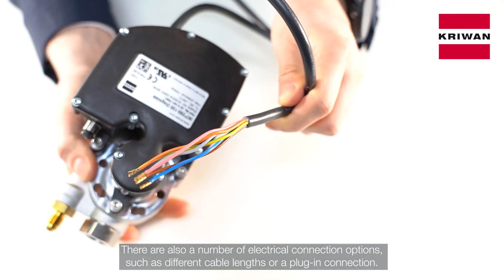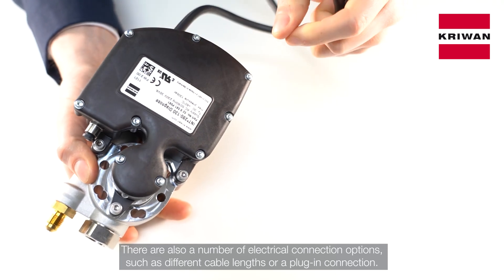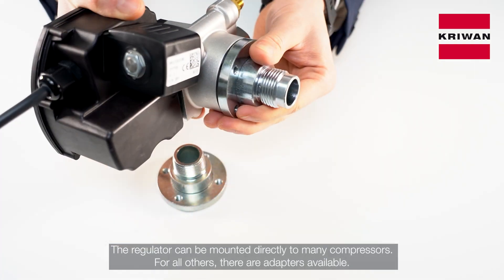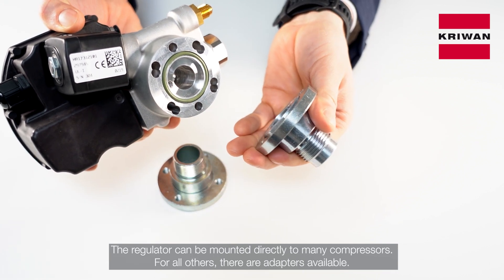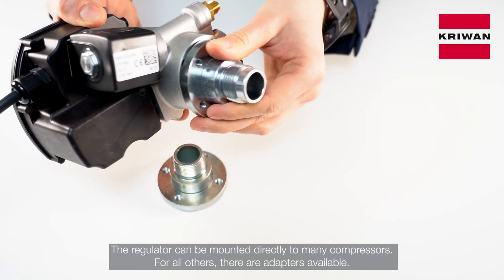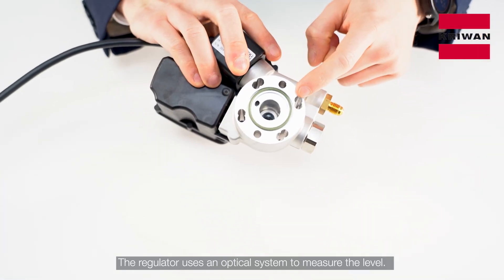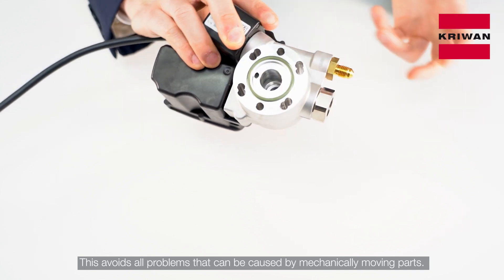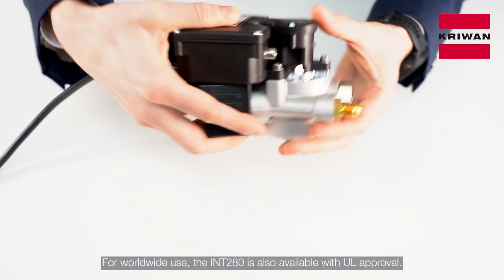There is also a number of electrical connection options such as different cable lengths or a plug-in connection. The regulator can be mounted directly to many compressors; for all others, there are adapters available. The regulator uses an optical system to measure the level — this avoids all problems that can be caused by mechanically moving parts. For worldwide use, the INT280 is also available with UL approval.